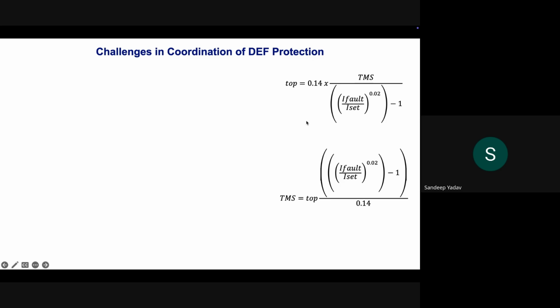So in this case, when we calculate the time multiplier setting, the I fault upon I set term is a mathematical expression which needs some looking into. In case of a synchronous generator, because the fault current is very high and much more than the rated current, the I fault upon I set term is greater than 1. Anything greater than 1 raised to the power 0.02 will be more than 1. So TMS will be positive.